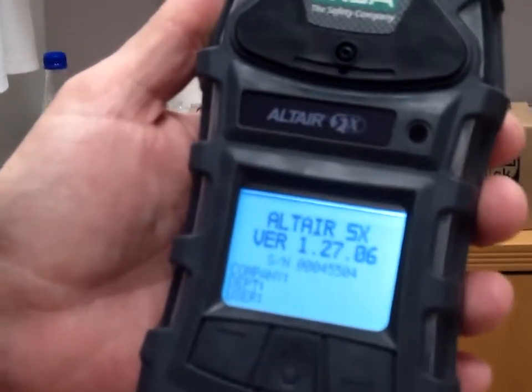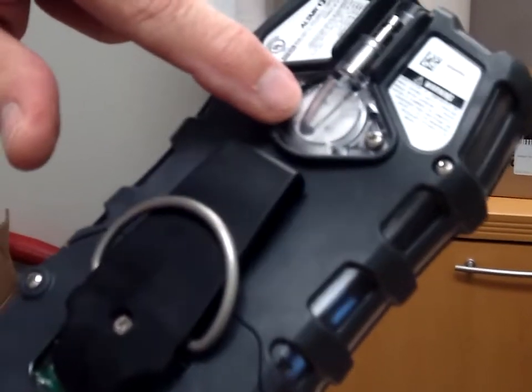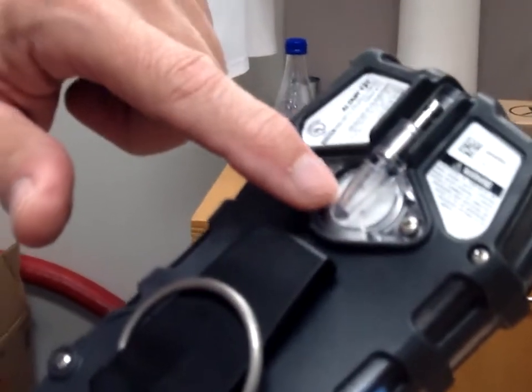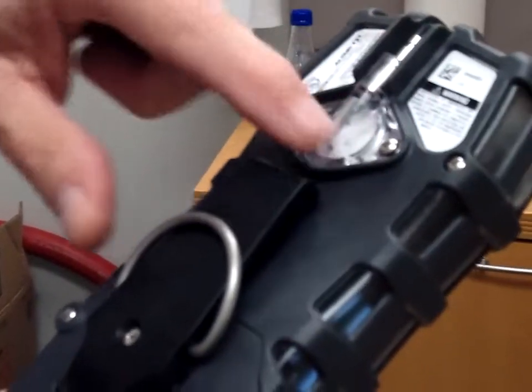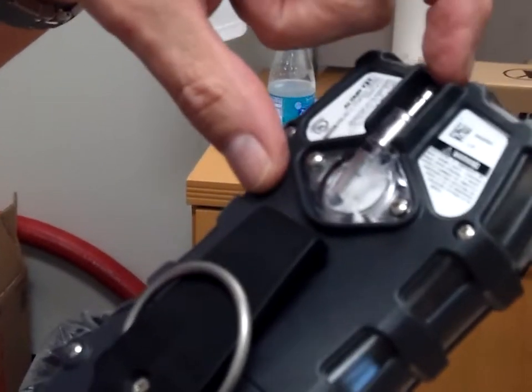So if you failed that pump test, your pump is bad, or maybe you just didn't block it properly? If you fail the pump test, that means that perhaps this filter is gone, or the gasket is missing, or something might be gone in there, allowing for air to escape around. You're trying to create a complete vacuum by doing that. Good question.